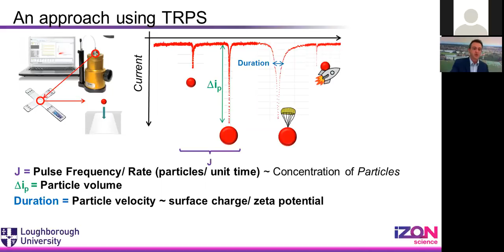You can get the size of the particle, I should say the particle volume, from the delta IP. And the duration, which is the thickness of this pulse, gives me an indication of the speed at which the particle is going through. So something that's going through really slowly, dragging something along with it, would have a very wide duration. Something that's racing through there would have a very narrow pulse, and we would say that was a higher particle velocity. So this pulse width is a measure of how quickly the particle is going through the pore, and we've just introduced that if you can measure velocity, you can work out the zeta potential. Now the leap from measuring how quickly something goes through a pore via the duration and converting that into a zeta potential, hopefully it's not too much of a jump, and actually would seem quite logical for us.